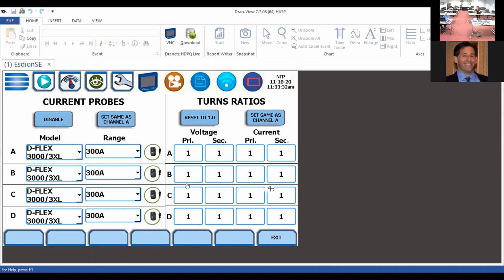A typical ratio that you would see in 4160 is 4160 to 120, or it might be 4160 to 60. That's a very common ratio. Common ratios that you might see for current are 3,000 to 5, 2,000 to 5, 1,000 to 5. Those are very common ratios as far as CTs are concerned. But once you've entered the correct information, then you would go to exit. In some cases, the exit button also serves as an enter button.